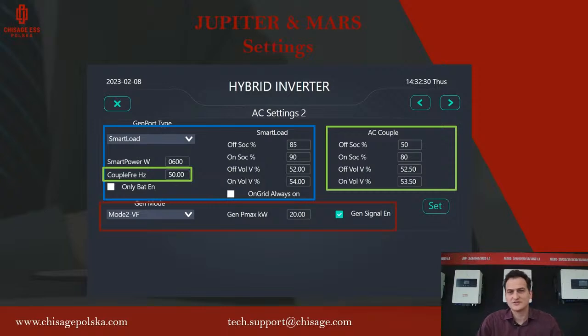Second page, we set up the smart load, gen set or AC couple. So that's the gen port mode. On the left top we have smart load, AC coupling, or generator. And if we pick generator, we have to fill in this information at the bottom: gen mode, gen power maximum, and whether we want a signal to start the generator or not.